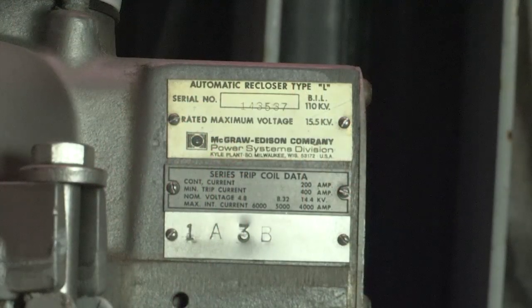So what we're looking at here is a standard L-type hydraulic 200 amp A1B3 recloser. Now you can see that there's 200 amps of continuous current that's allowable for this recloser, and it also has a 400 amp maximum rating. So anything over 400 amps, it will trip on load or a fault. Now as far as the A1B3 is concerned, it's basically one fast curve and 3 delay curves.